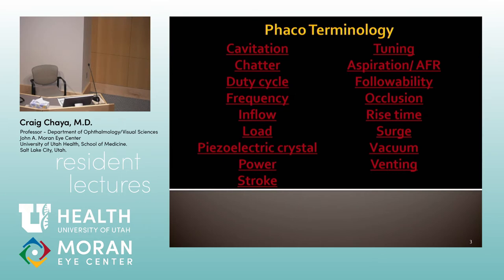The rate at which vacuum builds once the aspiration port has been occluded — that's rise time. It's controlled by your foot and your settings on the machine. Your machine settings can be more aggressive so that once you occlude a piece, you really quickly want to build that vacuum to your tip. It's just helpful to know how to set up the vacuum machine.